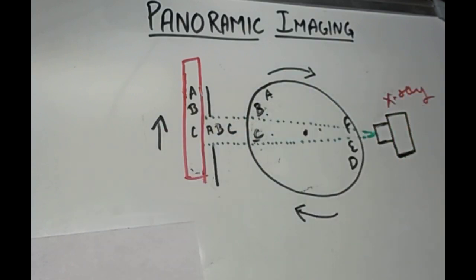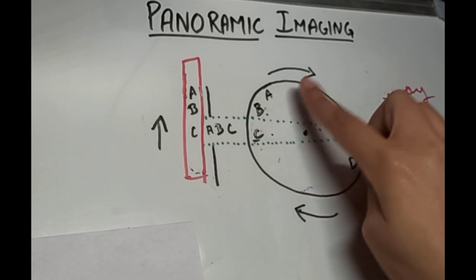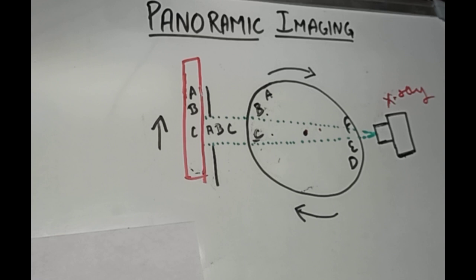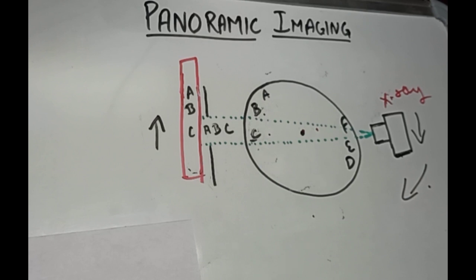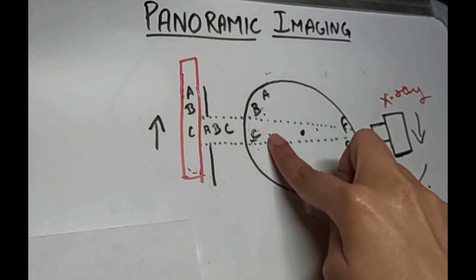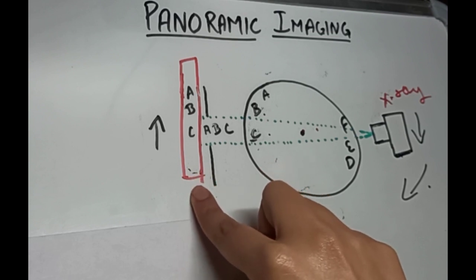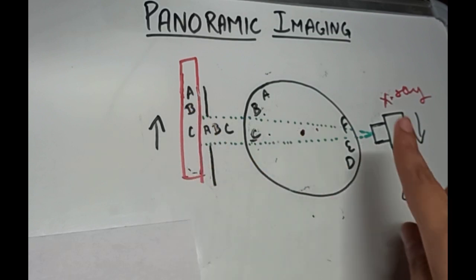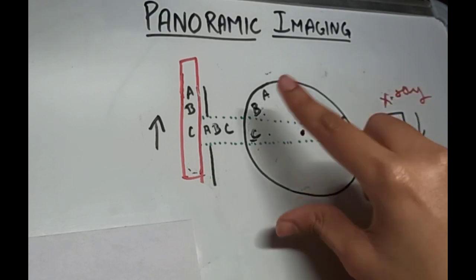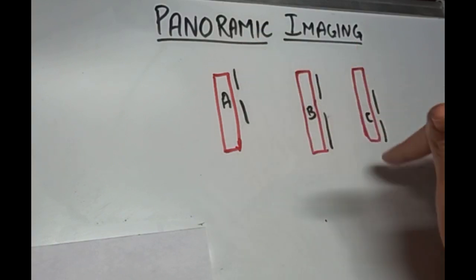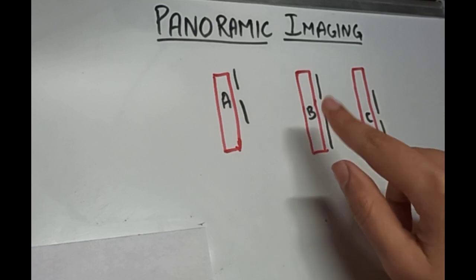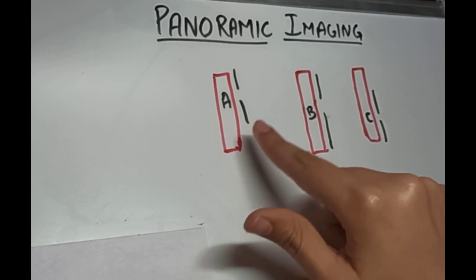When imaging a patient we cannot ask the patient to move, so we move the x-ray source instead. To receive the image on the receptor as the x-ray passes through objects A, B, and C, we also move the image receptor. So the x-ray source, the receptor, and the collimator all rotate around the patient. You can see how the receptor moves past the collimator during their motion around the patient.